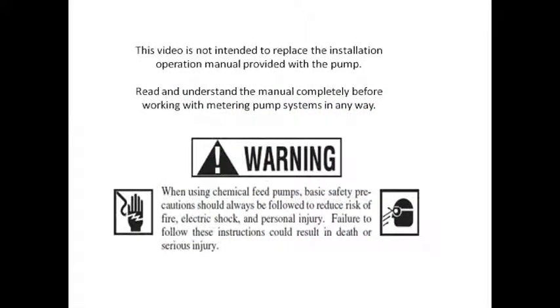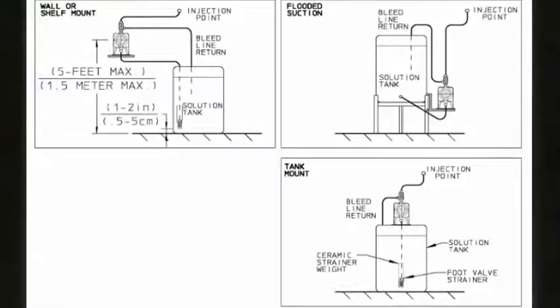This video is not intended to replace the installation operation manual provided with the pump. Read and understand the manual completely before working with metering pump systems in any way. When installing a metering pump, the location of the pump is one of the most important considerations. For wall or shelf mounting, connect the suction tubing to the suction valve of the chemical pump. Tubing should be long enough so that the foot valve strainer assembly hangs about 1 to 2 inches above the bottom of the chemical tank.